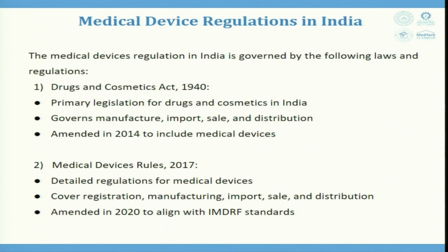Similarly, we have an administration in India, which is governed by the following laws: the Drugs and Cosmetics Act 1940, and the Medical Devices Rules 2017. This is a very important document here. The first one, the Drugs and Cosmetics Act, is the primary legislation for drugs and cosmetics in India, and it governs manufacture, import, sale and distribution. It was amended in 2014 to include medical devices.